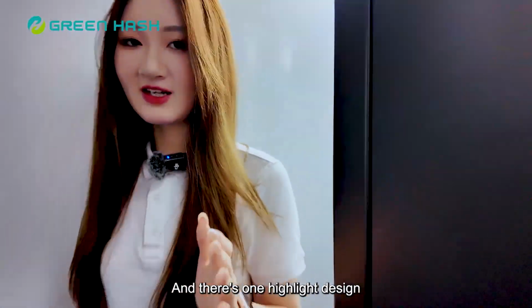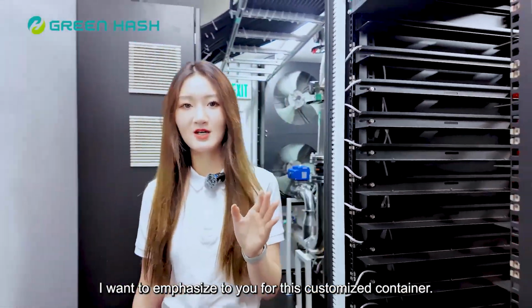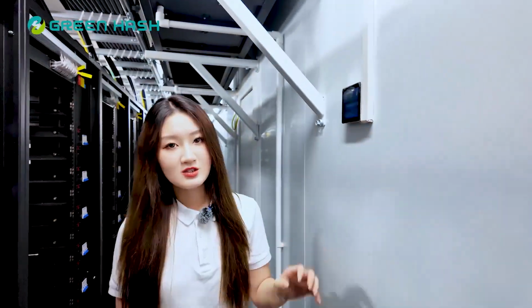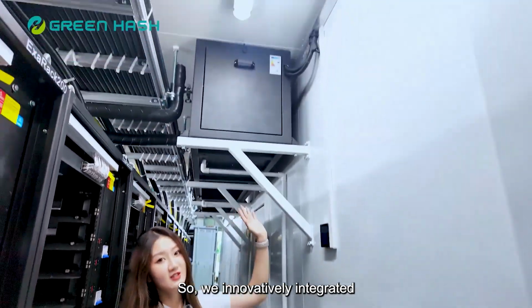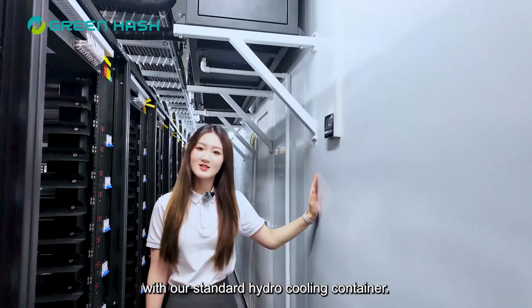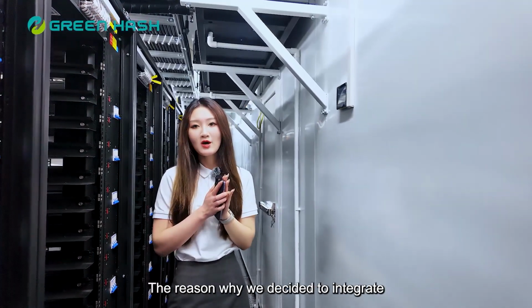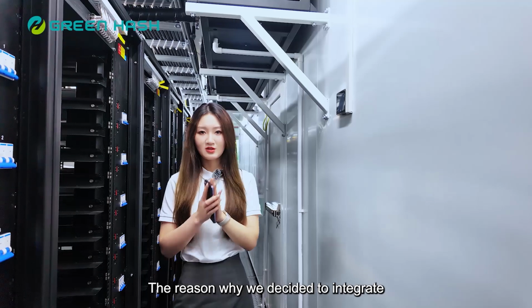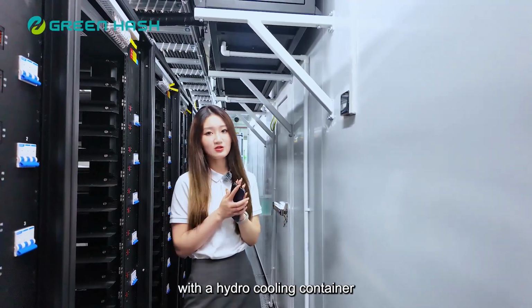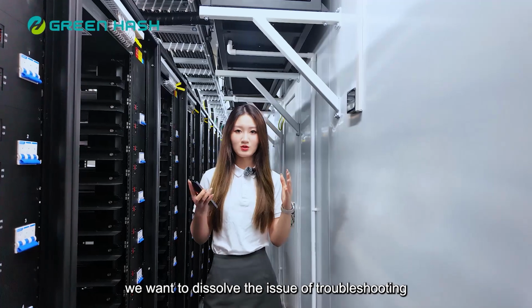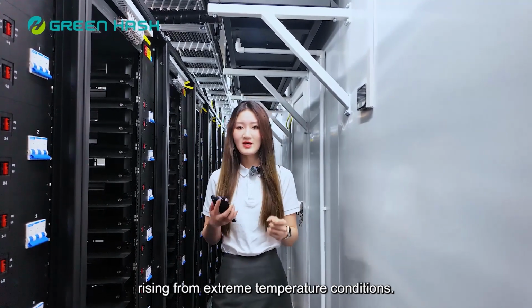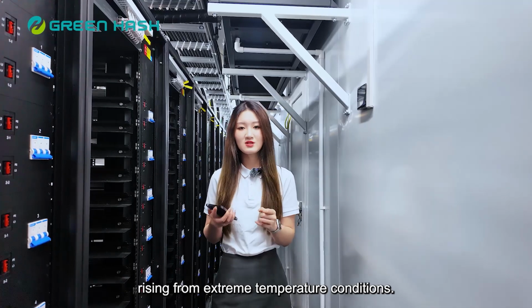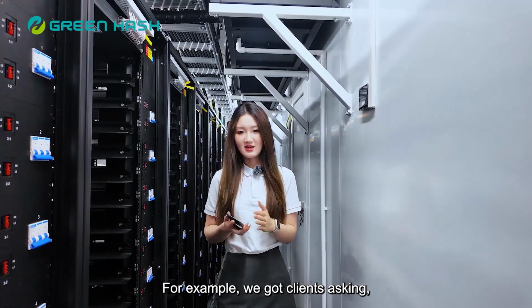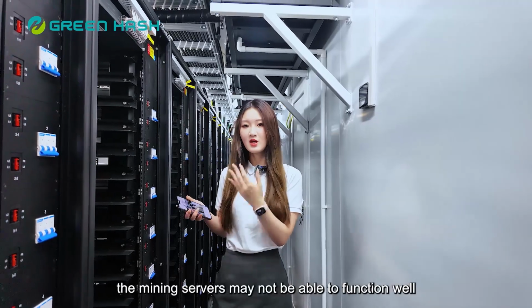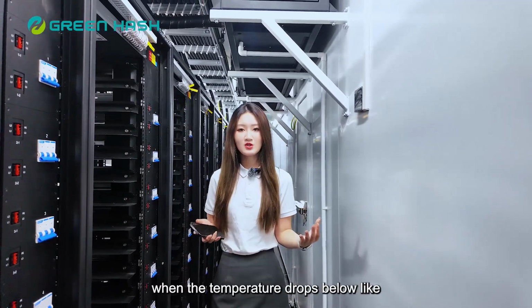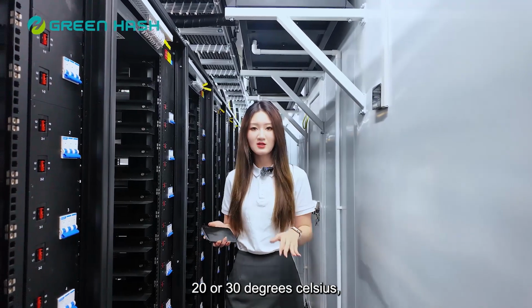There's one highlight design I want to emphasize for this customized container. We innovatively integrated a heat pump air conditioner with our standard hydro cooling container. The reason we decided to integrate a heat pump air conditioner with a hydro cooling container is because we want to solve the troubleshooting issues arising from extreme temperature conditions. For example, we got clients asking that the mining servers may not be able to function well when the temperature drops below like minus 20 or 30 degrees Celsius.